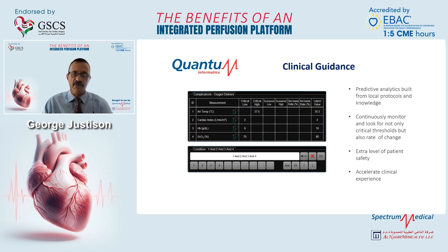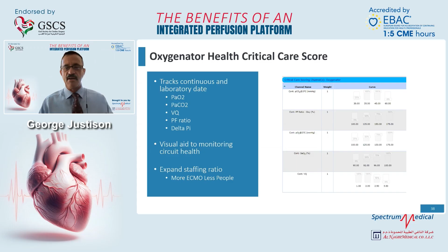So one example of these is what we call the Oxygenator Health Critical Care Score. And this is something that we use in ECMO. And what it does, it continuously tracks continuous data such as PaO2, PaCO2, as well as laboratory data, and calculates a value that tells you the health of the oxygenator. And so what it's doing in the background is essentially taking over the role for you, or assisting you in the role of monitoring oxygenator health and predicting potential oxygenator failure.